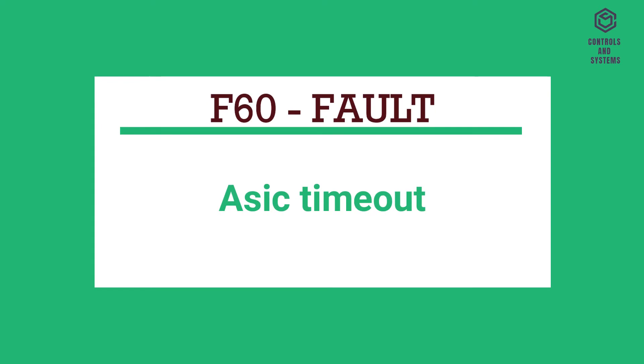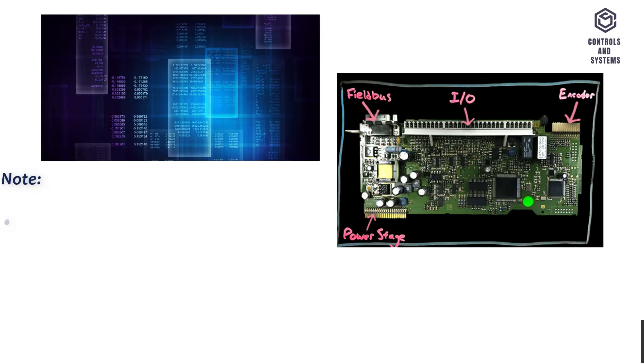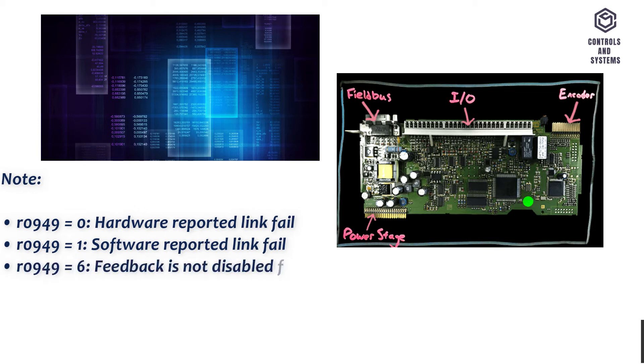F60 Fault: ASIC Timeout. Cause: Internal communications failure. Remedy: Check inverter. Fault appears sporadically. Note: R0949 equals 0: hardware reported link fail. R0949 equals 1: software reported link fail. R0949 equals 6: feedback is not disabled for reading inverter data.